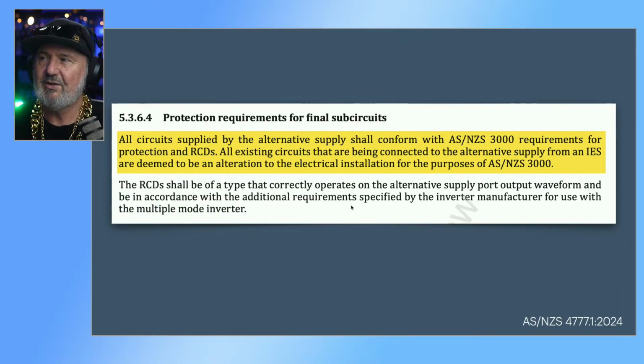And then it goes on to say protection requirements for those final sub-circuits. All circuits supplied by the alternative supply shall conform with AS/NZS 3000 requirements for protection and RCDs. So maybe, Stephen, to answer your question, it's not actually mandating RCDs, it just needs to meet the requirements of 3000. So if 3000 says you need an RCD on a stove, then you need an RCD. If it says you don't need an RCD for a particular application, then you don't. So it really just falls back onto 3000. I hope that clarifies your question, Stephen.